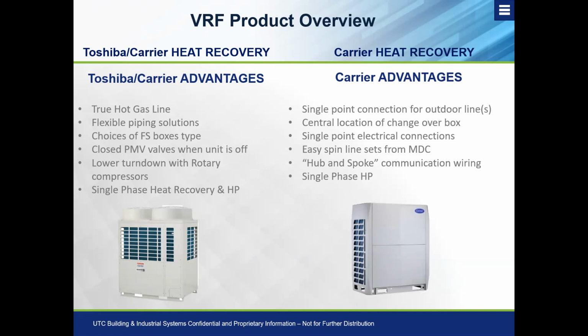And then Carrier advantages. We have our single point connection for power, communication, and control, and also pipe. We have a centralized location for a changeover box, and we have options of total ports that you can have. With the Toshiba Carrier, those multi-port boxes have a 4 or 6 port configuration, while the Carrier system has a 6 through 16 port connection on their box depending on the application. So we can facilitate more indoor units and locate that box centrally. By having that hub and spoke communication wiring from the MDC to the indoor units, we can essentially follow our refrigeration pipe from port 1 to indoor unit 1, port 2 to indoor unit 2, so they're not dealing with that daisy chain, and it essentially eliminates some of the complexity with control wiring on these systems.